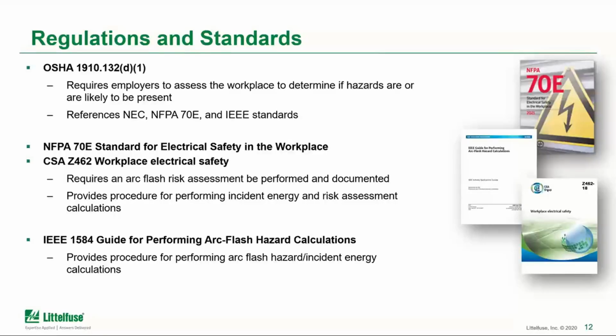So finally, that is a specific guide for performing arc flash hazard calculations. In that text, it provides the formulas and a lot of tables and correction factors that allow you to identify what the actual arc flash hazard and incident energy ratings are. There are also software tools, of course, that are available to do that calculation, and they will base that off of the IEEE 1584 formulas. So that gives a little bit of a flavor of how those all link together.